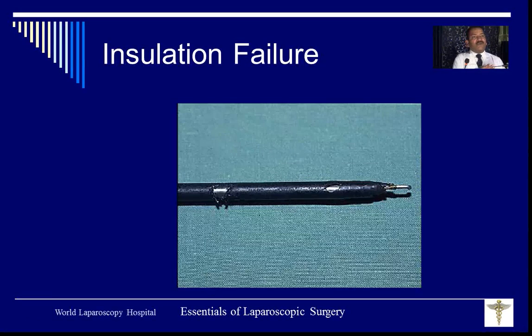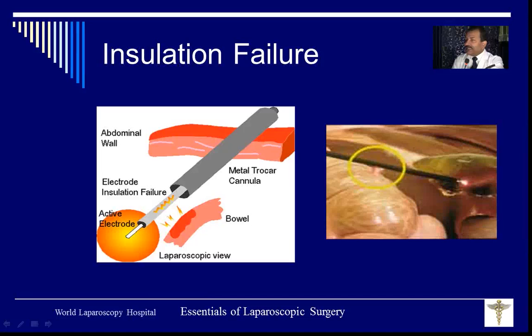Sometimes what we do is activate our electrode in open circuit - suppose I have to hook it, first I press the pedal, and then I go. This is extremely dangerous, because in that fraction of a second it takes to reach the tissue, if there is insulation failure, current will jump even one to two centimeters and burn. But if you first hook the tissue before activating, current will not jump through a small insulation failure.